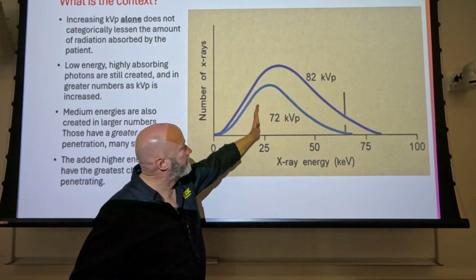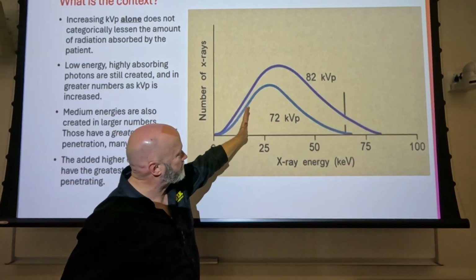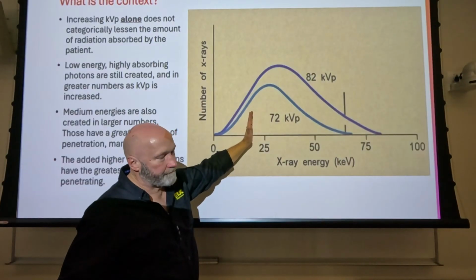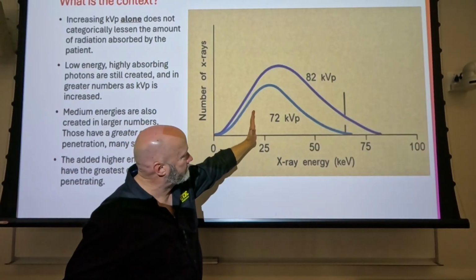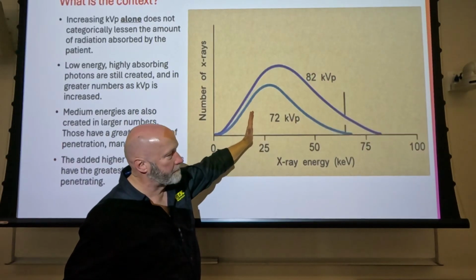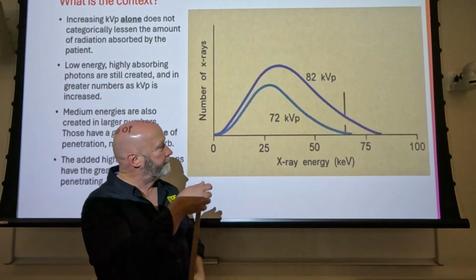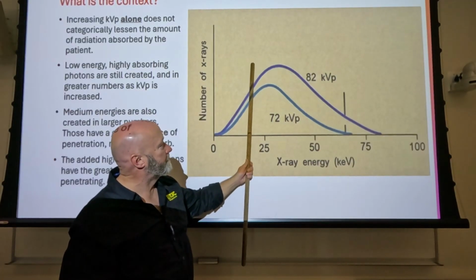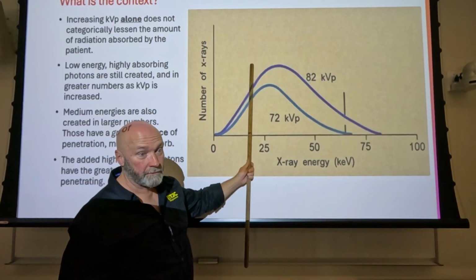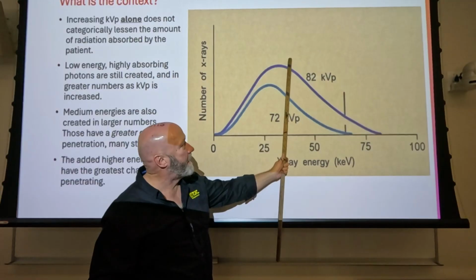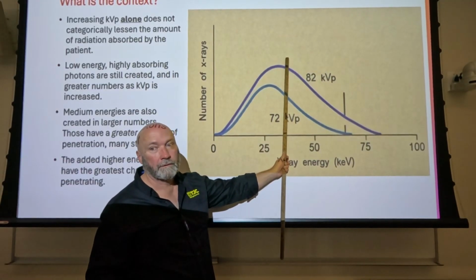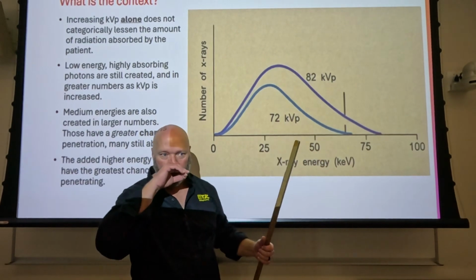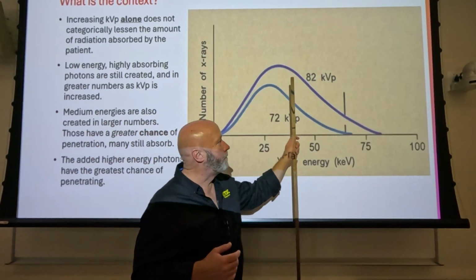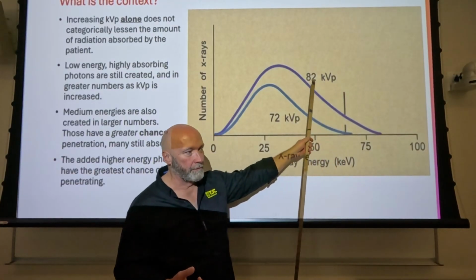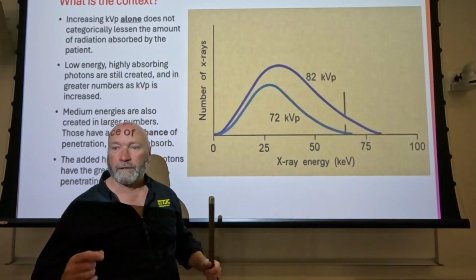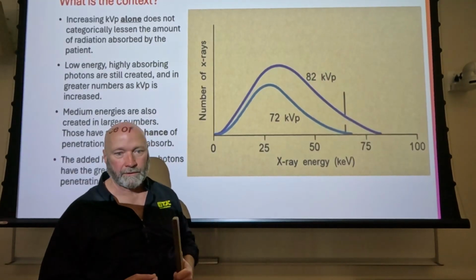So if we could say that, I wish we had more numbers on here. Let's say, in this oversimplified explanation, 20 kVp, all of the 20 kVp and below absorb into the patient. What happens to the patient dose? Goes up, right? So let's say from 20 to 40, about half of them, what happens to patient dose? Goes up. And let's say above 40, everything penetrates, right? So what we get is more penetration, absolutely true, but we also get more exposure to the patient. If the only thing that we do is increase kVp, what happens to patient dose?